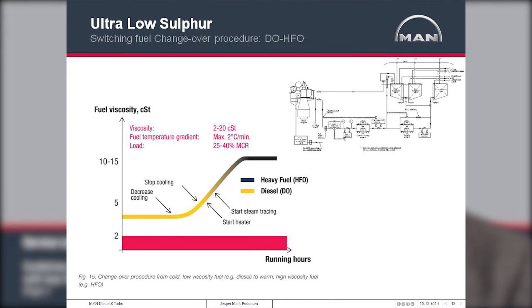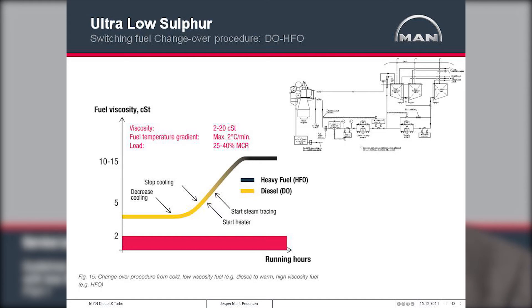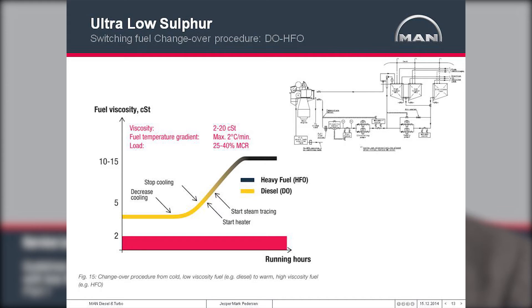During this switch, you cannot increase the temperature by more than two degrees per minute. If you do so, there is a risk that the clearance inside the fuel pumps between the plunger and barrel becomes too small, and they will start to seize and eventually stick. It is therefore important to keep to two degrees per minute to make sure that this doesn't happen.